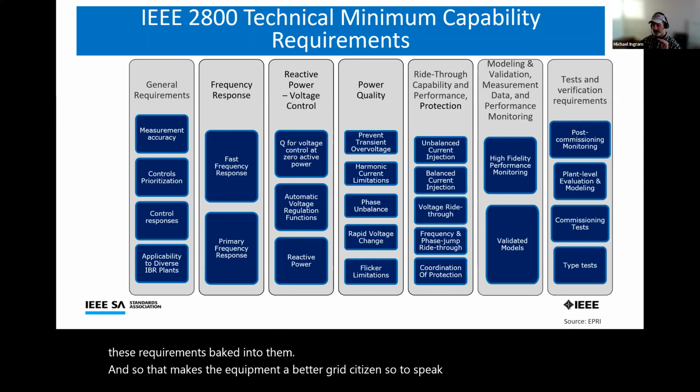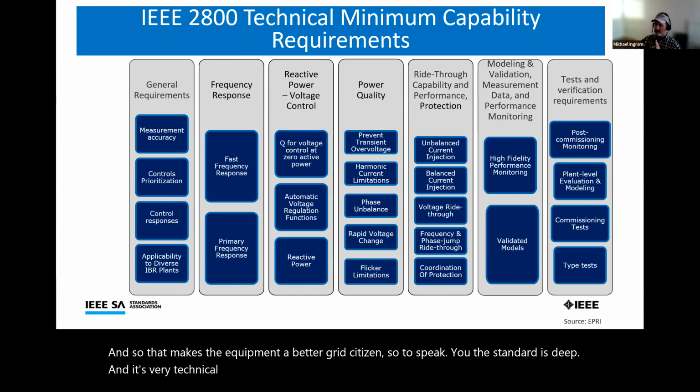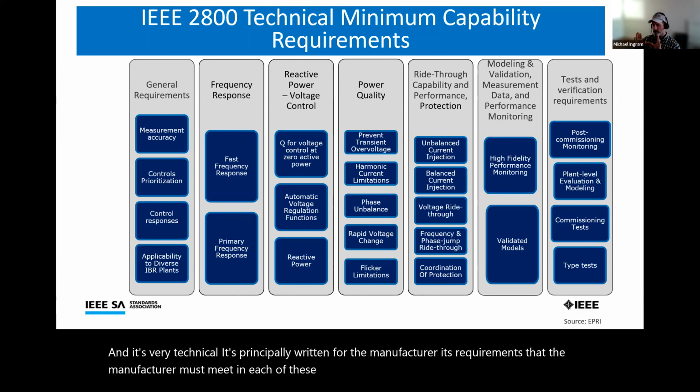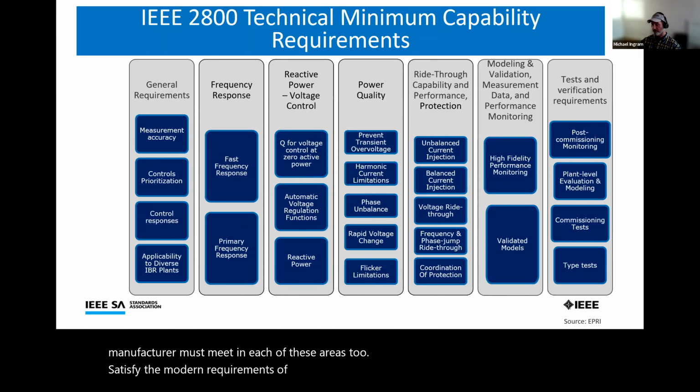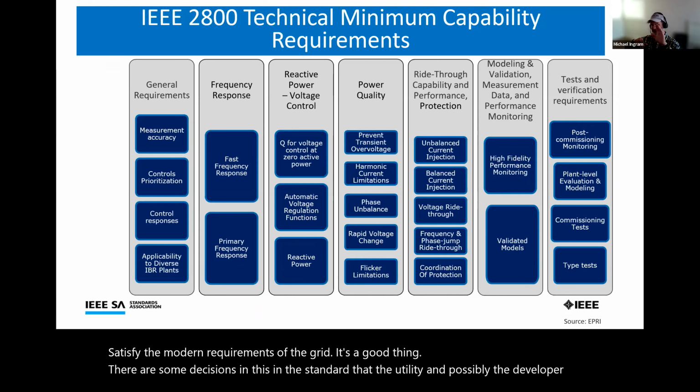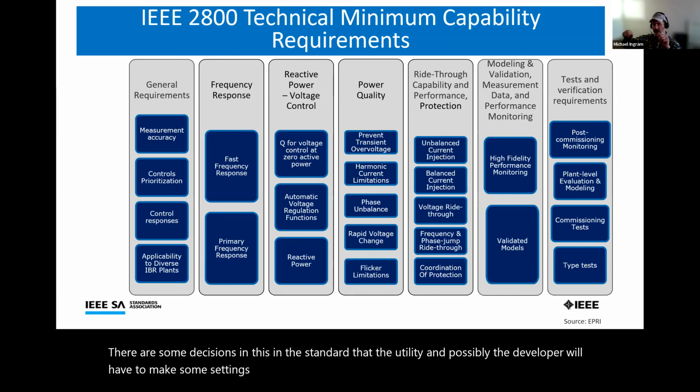The standard is deep and very technical. It's principally written for the manufacturer. It's requirements that the manufacturer must meet in each of these areas to satisfy the modern requirements of the grid. That's a good thing. There are some decisions in the standard that the utility and possibly the developer will have to make, some settings, some knobs and dials, if you will, that will need to be modified when the connection is made.